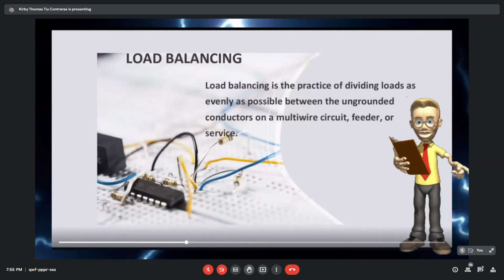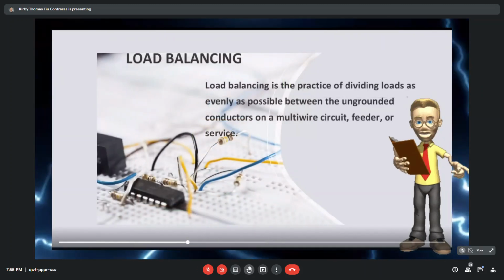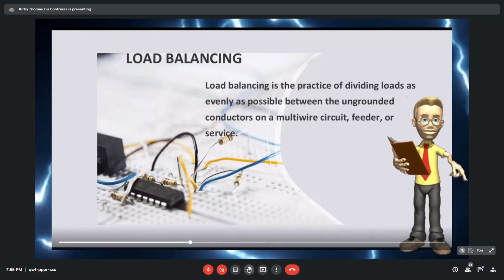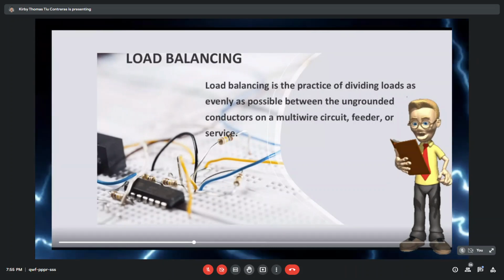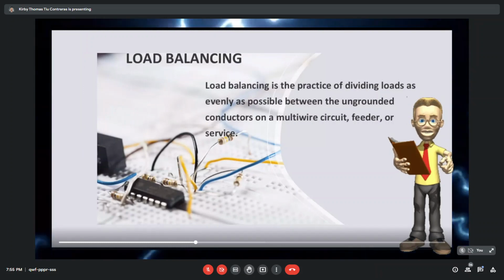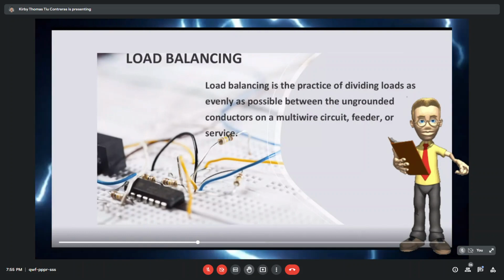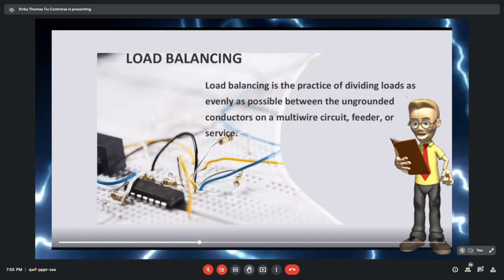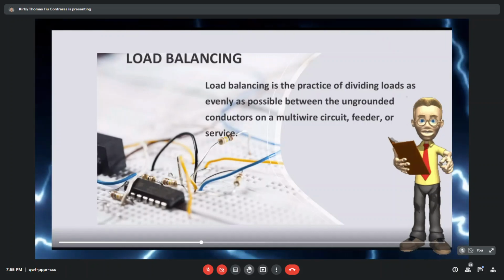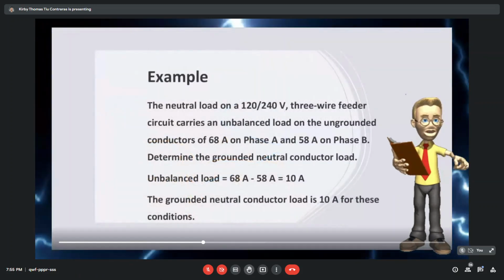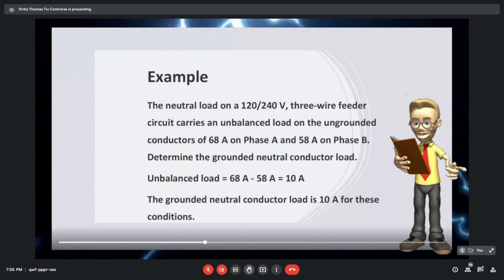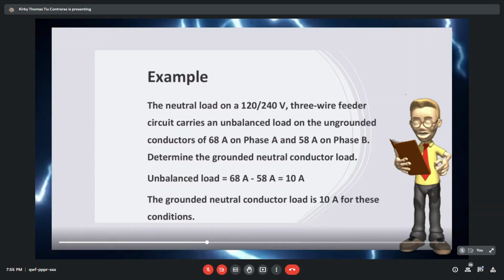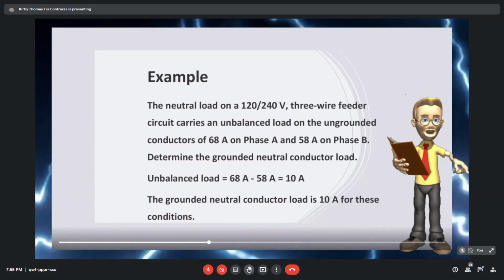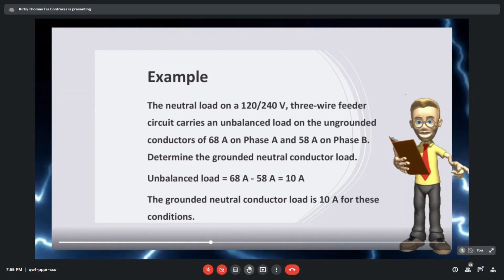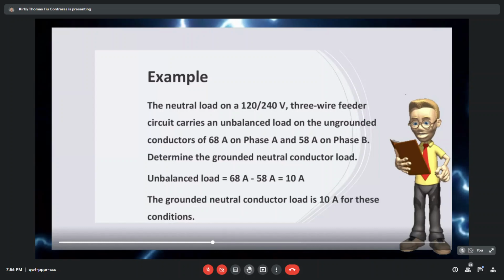So a neutral conductor cannot by definition serve a single 120 volt circuit because it has only one grounded conductor. A neutral conductor is a grounded conductor that is shared between two or more ungrounded conductors. A neutral conductor is frequently called a shared neutral or a common neutral. So in a 120 over 240 volt, 3-wire service entrance, feeder or branch circuit, there is a neutral conductor and two ungrounded conductors.